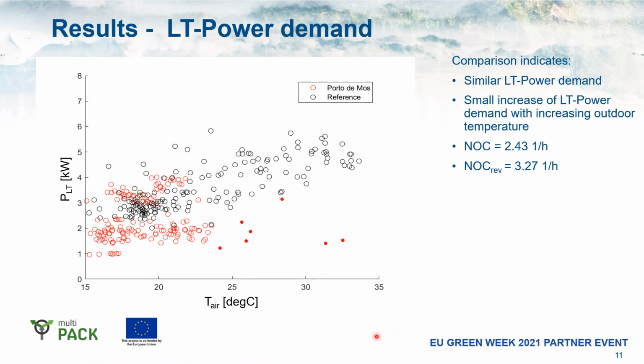If we look at the low temperature compressor power demand, which is plotted here over the ambient temperature, we see that they are very similar. So it's not a big deviation between the LT electric power demands. The increase over the ambient temperature is also comparable. However, the reference shop consumes more LT power at higher temperatures than the Portugal side. If we compare the number of cycles, so how often the compressors are turning on and off, we see that this number is substantially lower for the MultiPACK side. It is in the order of 2.4 on and off per hour, while on the reference side it is 3.3.